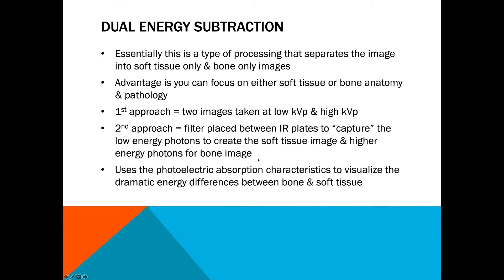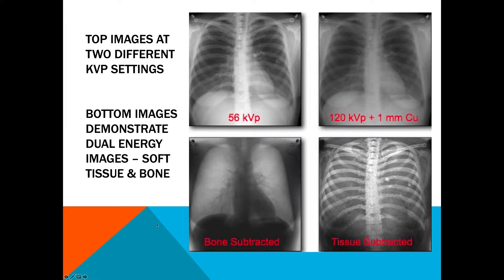Dual energy subtraction uses the photoelectric absorption characteristic to visualize the dramatic shift between bone and soft tissue. Here's a good example showing the low kVp and high kVp images side by side, along with what it looks like when the bone is subtracted versus when the tissue is subtracted — focusing on soft tissue in one image and bone in the other. Dual energy is something you see quite a bit in CT and mammography.